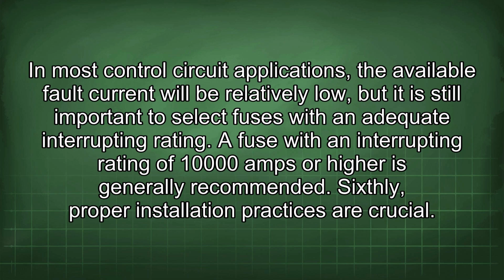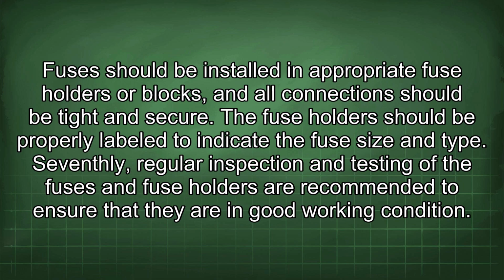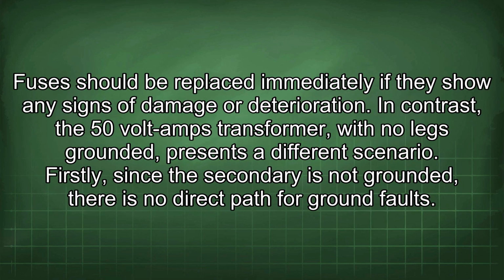Sixthly, proper installation practices are crucial. Fuses should be installed in appropriate fuse holders or blocks, and all connections should be tight and secure. The fuse holders should be properly labeled to indicate the fuse size and type. Seventhly, regular inspection and testing of the fuses and fuse holders are recommended to ensure that they are in good working condition. Fuses should be replaced immediately if they show any signs of damage or deterioration.